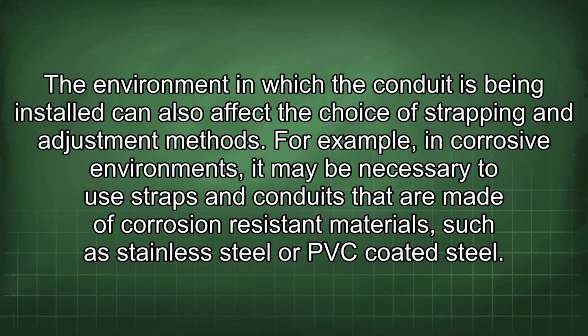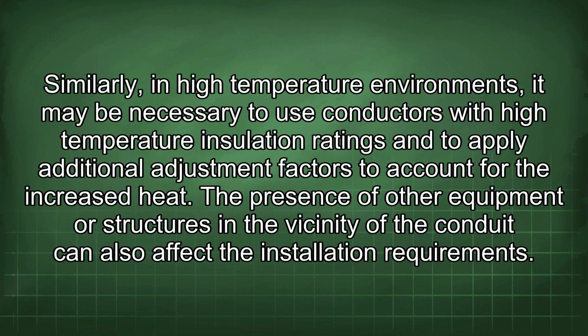The environment in which the conduit is being installed can also affect the choice of strapping and adjustment methods. For example, in corrosive environments, it may be necessary to use straps and conduits that are made of corrosion-resistant materials such as stainless steel or PVC-coated steel. Similarly, in high-temperature environments, it may be necessary to use conductors with high-temperature insulation ratings and to apply additional adjustment factors to account for the increased heat.